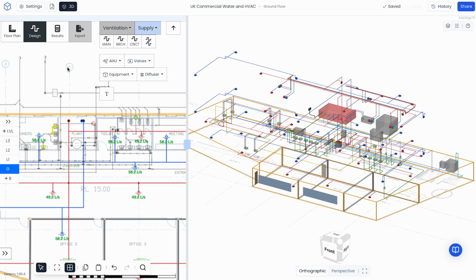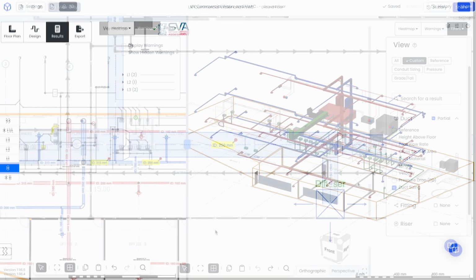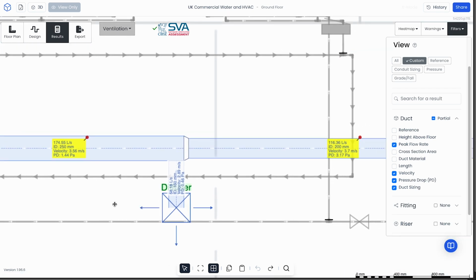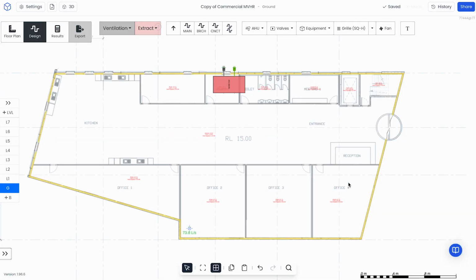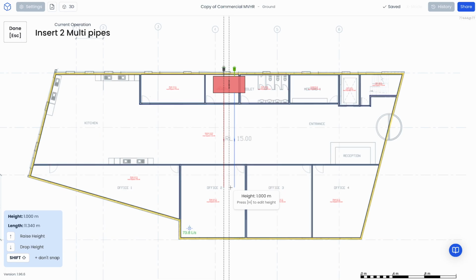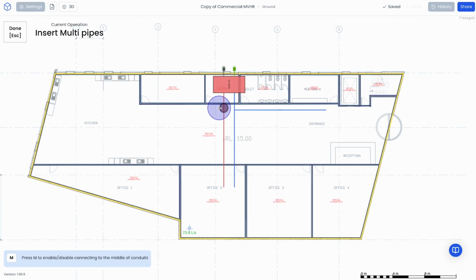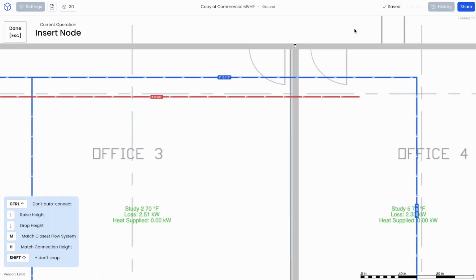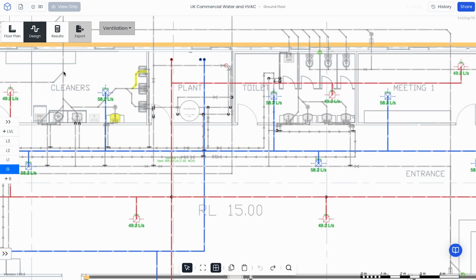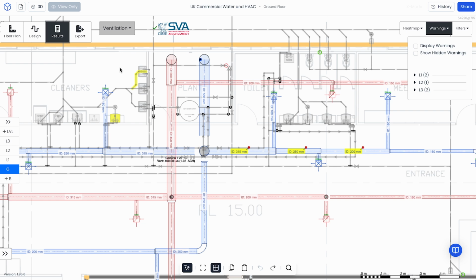And finally, there's modern design software like H2X, which has been designed specifically not just to solve the calculation of duct sizes, but to be a design platform that suits your workflow. The way that works is you upload the architectural drawings and you draw on top of them. As you're drawing, it's measuring the ducts automatically, and as you're connecting diffusers and other parts of your system, it's going to be calculating the flow rates. Then, based on your settings of maximum velocity, maximum pressure drop, and the preferred material, it's going to do all of your sizing calculations with the correct velocity and pressure drops.